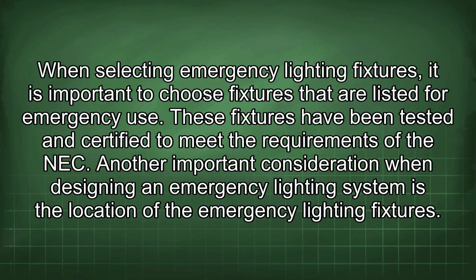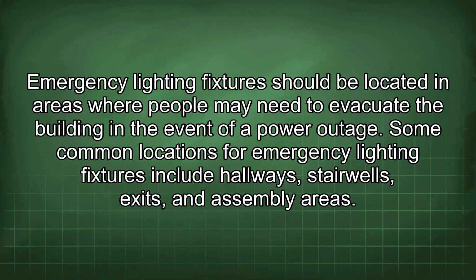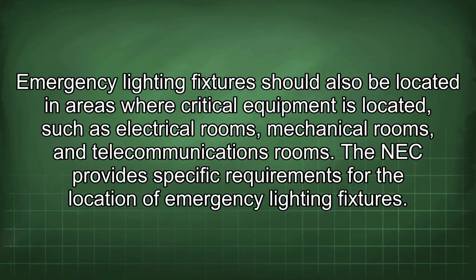When selecting emergency lighting fixtures, it is important to choose fixtures that are listed for emergency use. These fixtures have been tested and certified to meet the requirements of the NEC. Another important consideration when designing an emergency lighting system is the location of the emergency lighting fixtures. Emergency lighting fixtures should be located in the areas where people may need to evacuate the building in the event of a power outage. Some common locations for emergency lighting fixtures include hallways, stairwells, exits, and assembly areas. Emergency lighting fixtures should also be located in areas where critical equipment is located, such as electrical rooms, mechanical rooms, and telecommunications rooms. The NEC provides specific requirements for the location of emergency lighting fixtures.